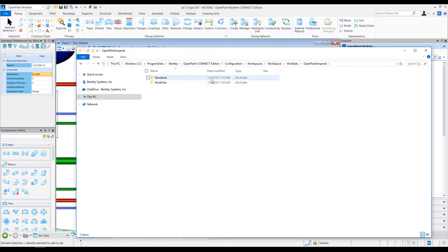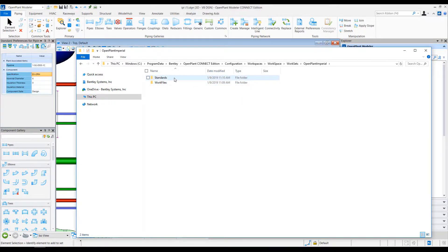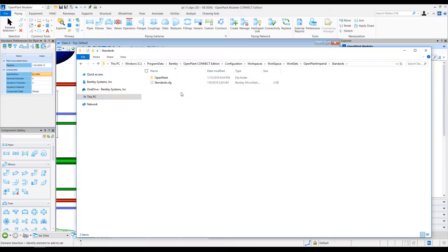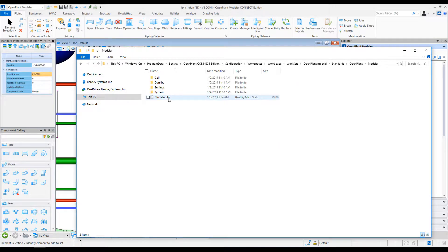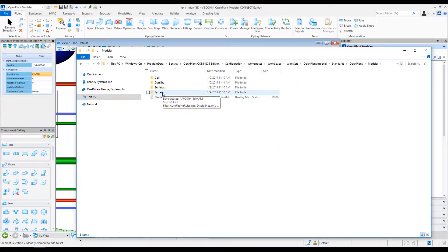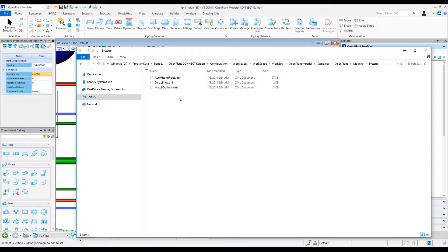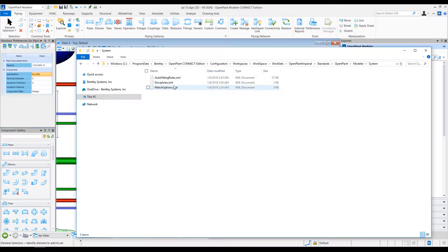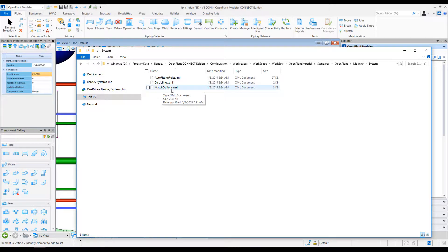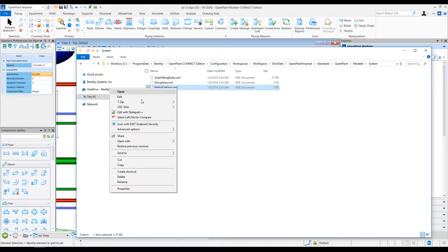In this workset, we have work files and standards folder. I will go to standards folder, select OpenPlant, and then go to modeler folder. In the systems folder, we have a few XML files which are system-related settings, some auto-fitting rules, and disciplines-related files. But the file of interest for today is match options XML. Let me edit this file.